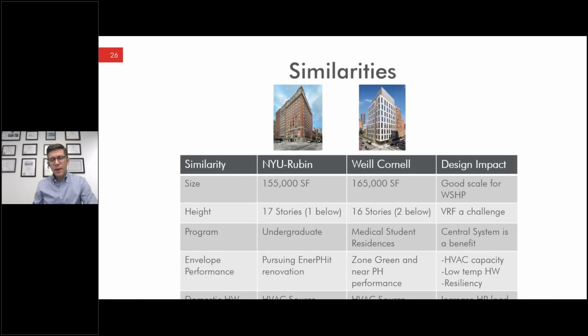Domestic hot water is always a big question on a residential building specifically, since those loads are a very big load within a residential building, and it's a challenge for an all-electric system: where do you get your air from for a heat pump system, where do you fit it, and how much storage do you need? Using an air-source, or air-to-water, heat pump for both HVAC systems allowed us to size our heat pumps to bring water to water-to-water heat pumps that handled domestic heating in both buildings. That let all the heat rejection or addition happen on the roof, feeding into the water-to-water heat pumps doing the domestic loads. It did increase heat pump capacity on the roof, but it simplified the domestic side and still gave us a very efficient all-electric building.